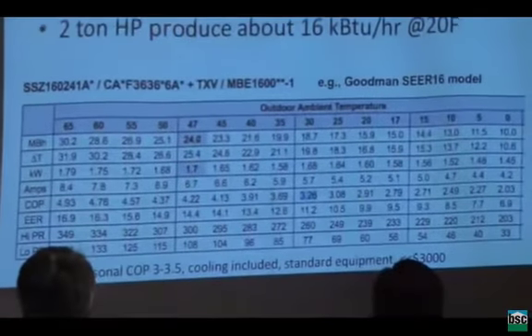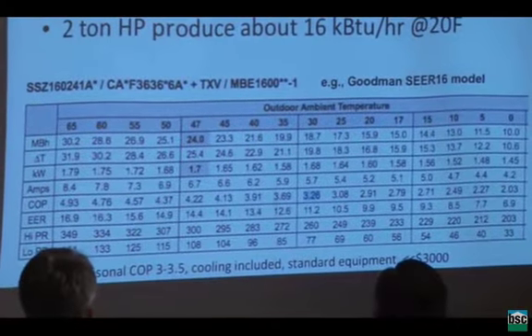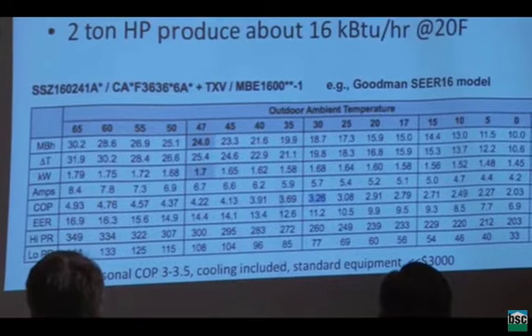But if I now take that same heat pump product and I move it to Boston, it would now deliver 16,000 BTUs an hour at 20. When I'm down at design temperature of 5, it would produce 11,500 BTUs an hour. So, okay, but then it'll overheat me a little bit when I'm at 40 degrees. Make sense? Now the other chart, and by the way, many of the manufacturers now have this type of data that you can look up. Just get their engineering manuals, and it's all free download. You don't need any special connections other than the internet.